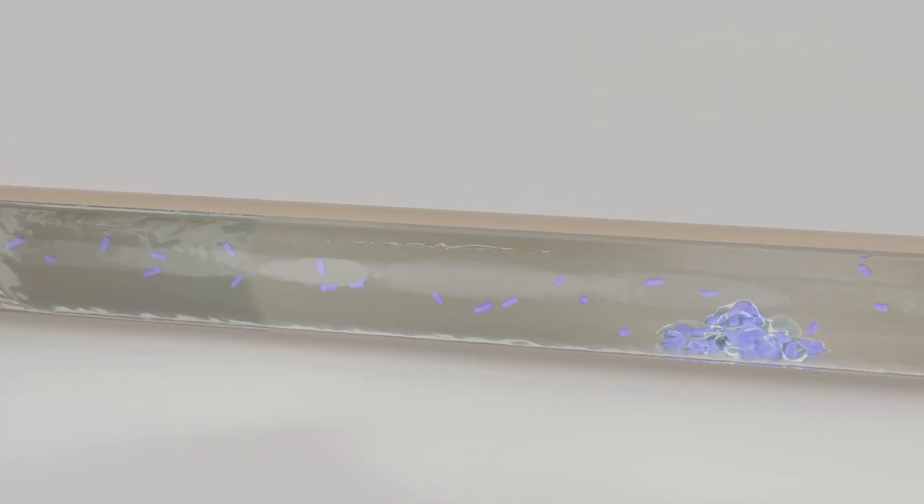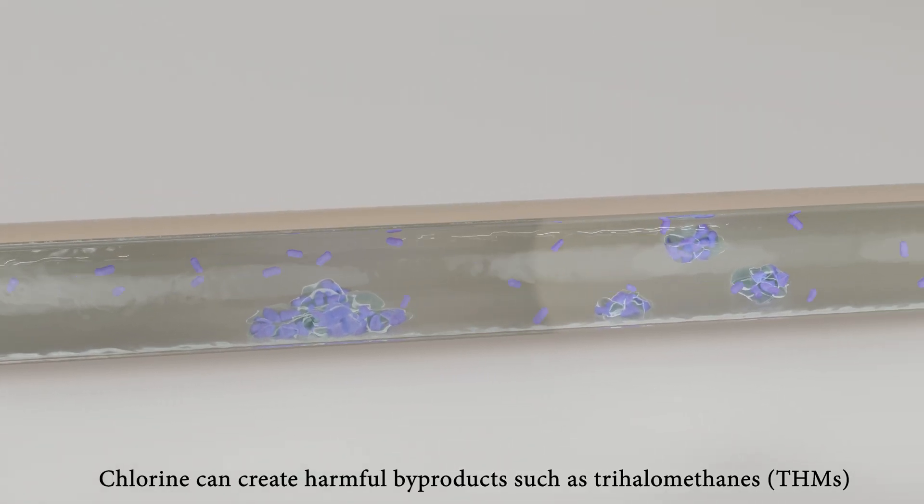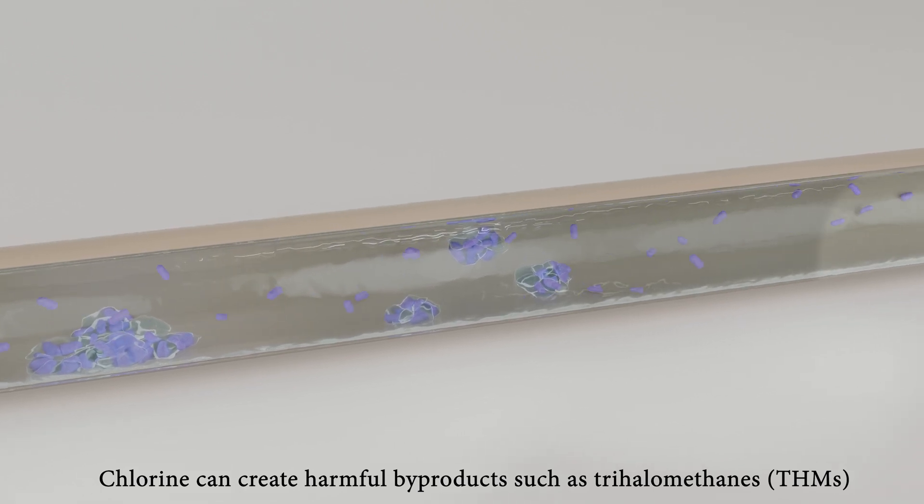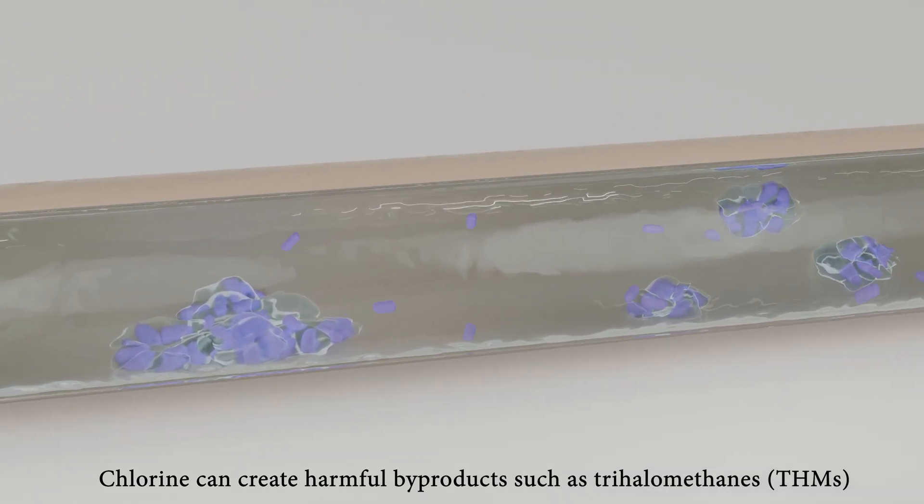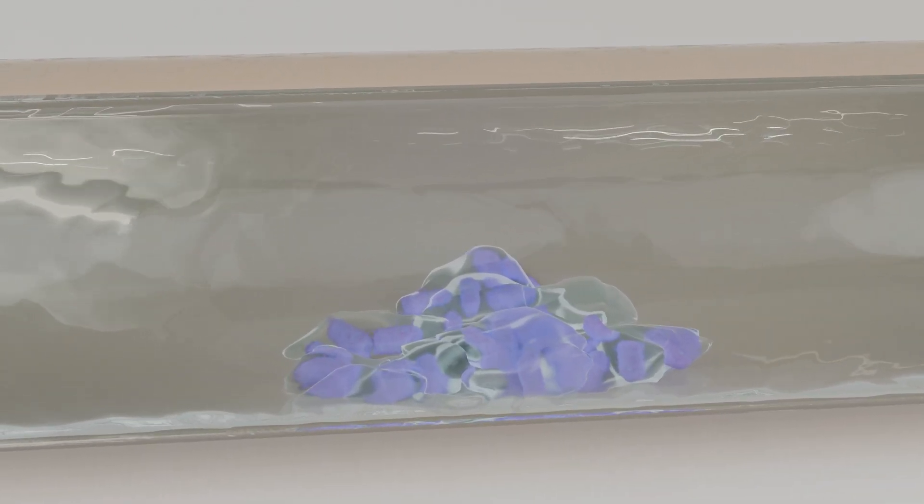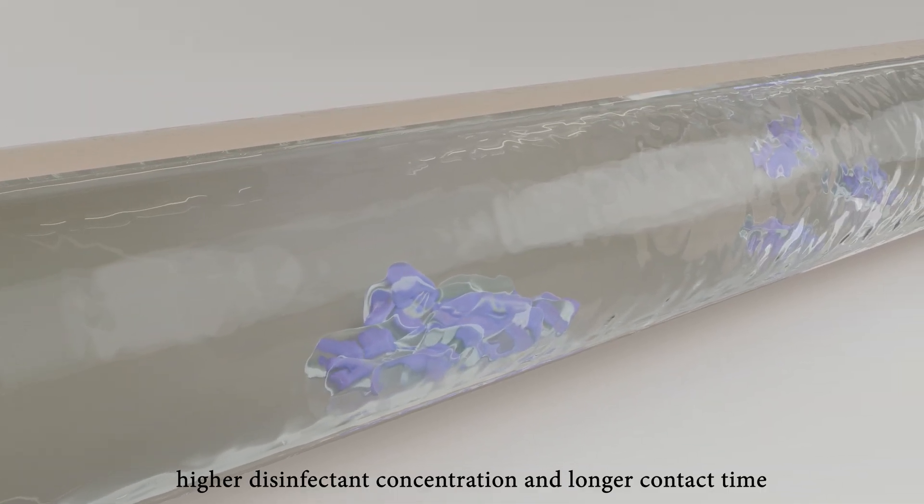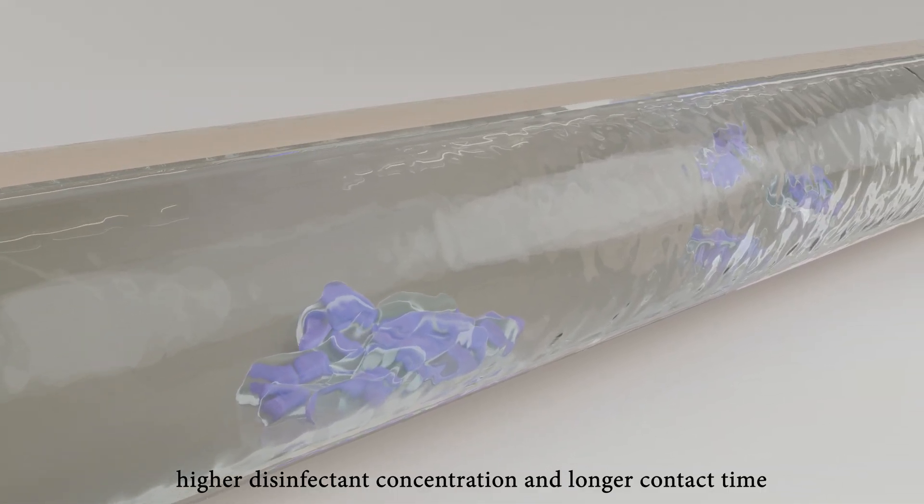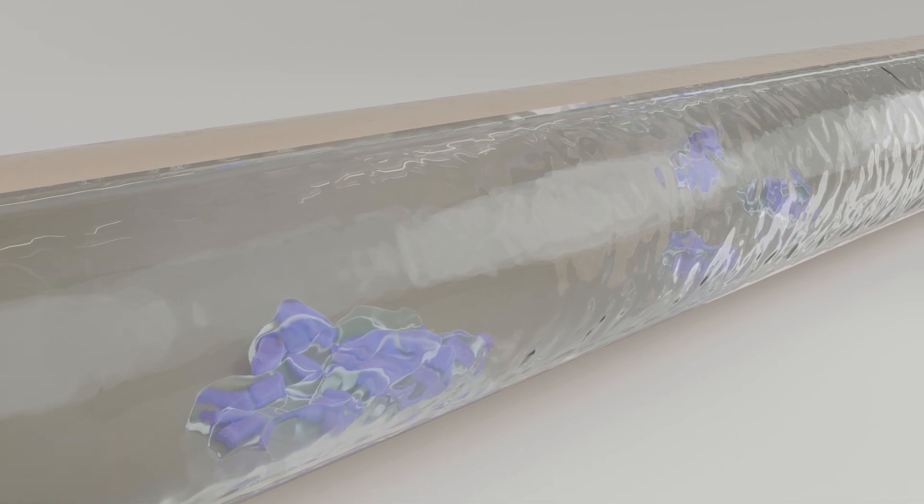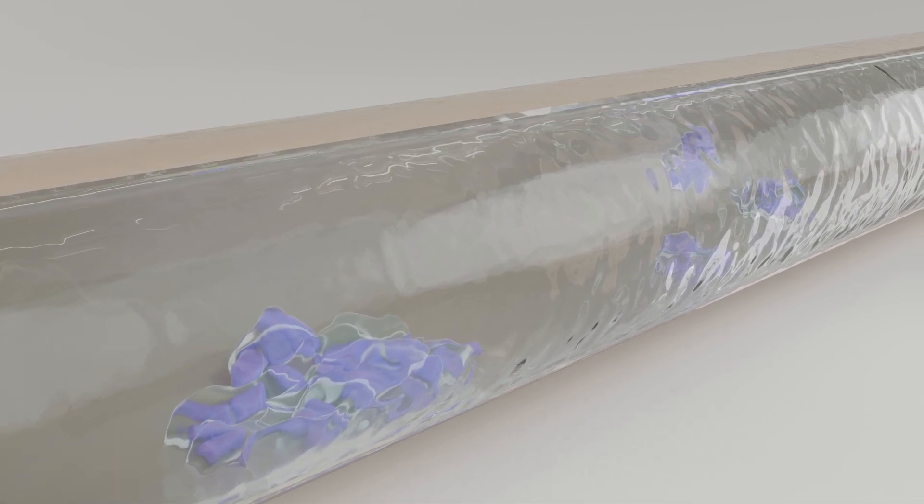The main disadvantage of all chlorine-based disinfectants is that they produce harmful and carcinogenic disinfectant byproducts. All chemical-based sanitizers need a higher CT value, meaning a higher disinfectant concentration and longer contact time, due to which most disinfectants are not effective on biofilm.